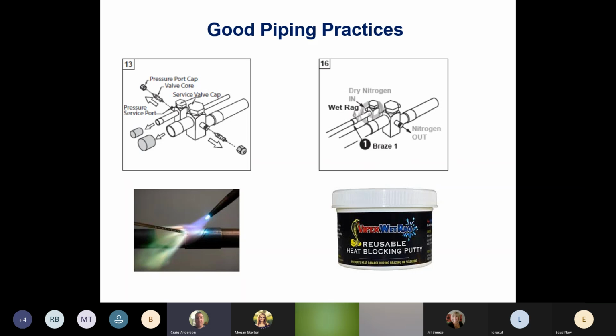So good practices as well when we're welding, like we talked about, we're blowing dry nitrogen through the lines. So we're keeping the inside of the copper clean so we're not getting any slag moving around the inside of it. We're taking the valve cores out. We don't want to overheat them. There's rubber on them. We don't want to overheat our valves outside either. So we're going to put a wet cloth around it.